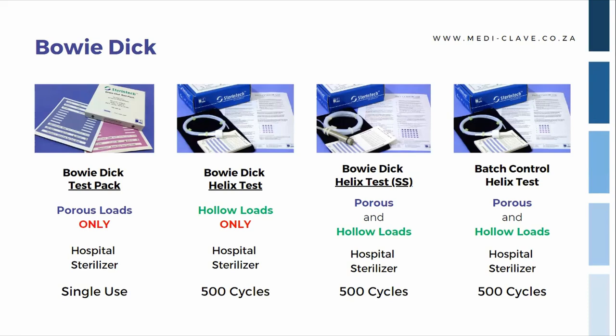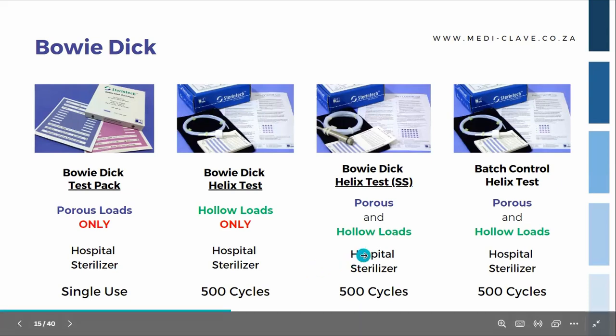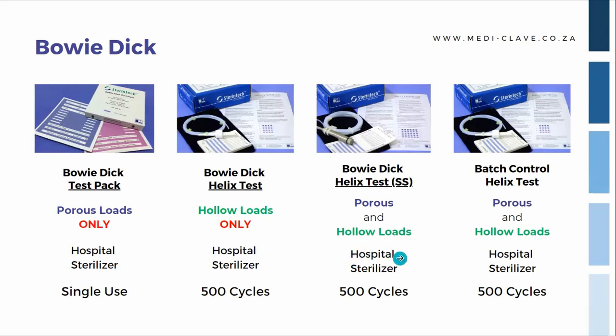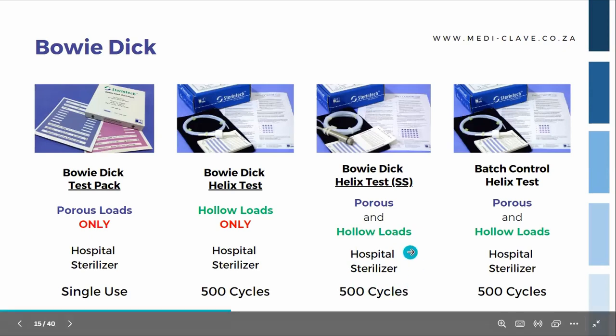So once they have been used and they are complete and you need to order a new set, you can't only order the indicators. The PCD, the pouch and the indicators is a whole set. So that gets thrown away and a new set gets taken out. Continuing to the Bowie Dick helix test, the stainless steel version. It's for porous loads and hollow loads, used in the hospital sterilizer, also for 500 cycles.